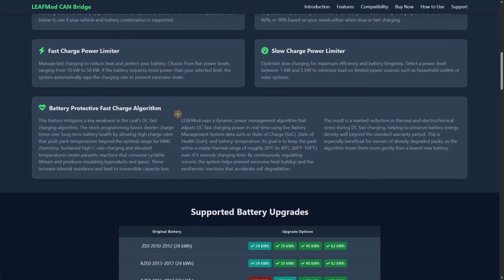LEAFMod uses a dynamic power management algorithm that adjusts DC fast charging power in real time using live battery management system data such as state of charge, state of health, and battery temperature. Its goal is to keep the pack within a stable thermal range of roughly 20 to 40 degrees Celsius, 68 to 104 degrees Fahrenheit, even if it extends charging time. By continuously regulating current, the system helps prevent excessive heat buildup and the exothermic reactions that accelerate cell degradation.